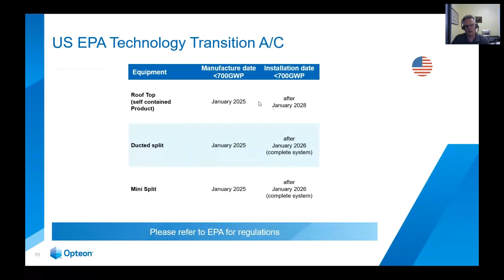You can see a couple of things: rooftops, ducted splits, mini splits. The manufacturing date is January 2025, less than 6 months away, and they can no longer manufacture equipment with a GWP greater than 700 in these sectors. They will allow sell-throughs of existing equipment up to 2028. But manufacturers are already converting to low GWP refrigerants to replace, primarily in this sector, 410A in new equipment, and they're certainly not going to build 3 years worth of equipment. So as the US transitions, manufacturers in Canada, the US, and around the world are transitioning their manufacturing facilities away from 410A to lower GWP solutions to meet these requirements.